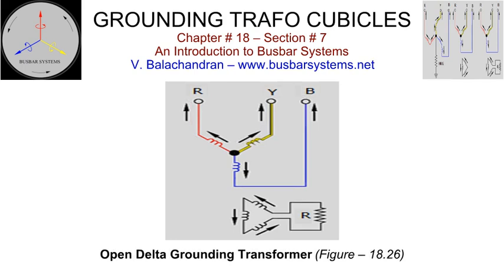Open delta grounding transformer. Single-phase transformers with shell-type construction can be installed in individual compartments of the surge protection voltage transformer cubicle when separately installed. The line terminal of the primary winding is connected to the tap-off bus and the neutral terminal is connected to the earth in each of the cubicles. The low-voltage windings are externally connected to form an open delta connection to provide path for the zero-sequence current to flow through the resistor.